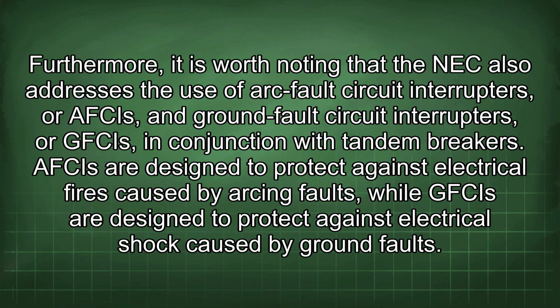Furthermore, it is worth noting that the NEC also addresses the use of arc fault circuit interrupters, or AFCIs, and ground fault circuit interrupters, or GFCIs, in conjunction with tandem breakers. AFCIs are designed to protect against electrical fires caused by arcing faults, while GFCIs are designed to protect against electrical shock caused by ground faults.